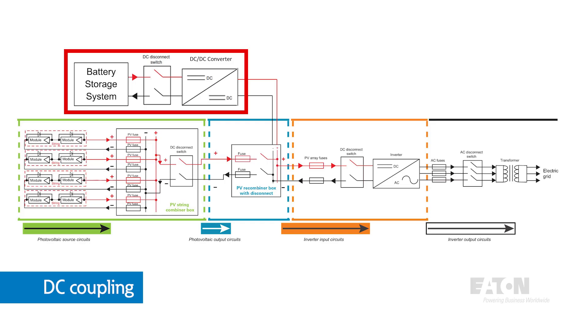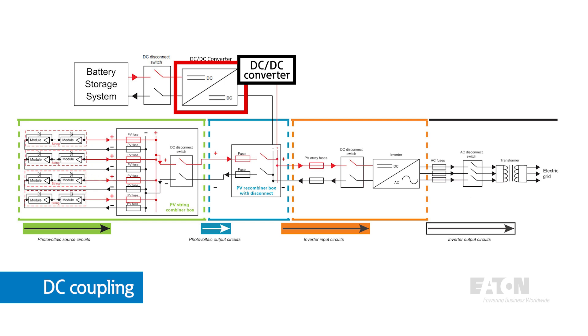DC coupling is when the battery storage system connects directly onto the same DC bus as the PV system before feeding the inverter. The current from the battery storage system goes through a DC-DC converter before connecting to the PV system. This type of connection tends to have higher initial installation costs, but will be more efficient over the life of the system. It's important to note that the circuit connecting the DC-DC converter output to the main PV system bus is considered part of the PV circuit and therefore must be a PV-listed device.